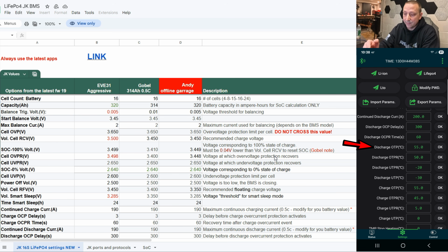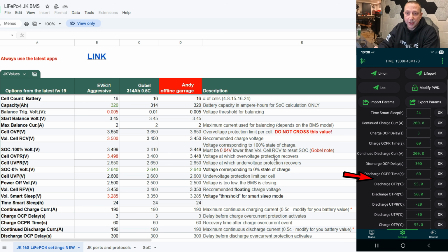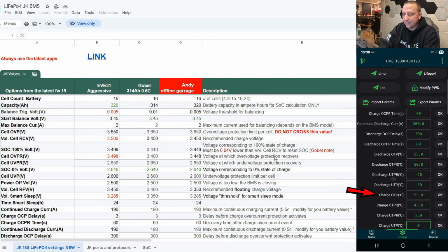So mine are set to 55 degrees C, and the release is set 5 degrees lower than that. If the batteries get real hot, they have to cool off to at least 50 C before they start going again. Same thing for discharge under temperature protection - they have it listed weird, but the release is set to -20, while the protection is set for -30, discharging down to that temperature. Charging is slightly different, but again I have it at 55 C.